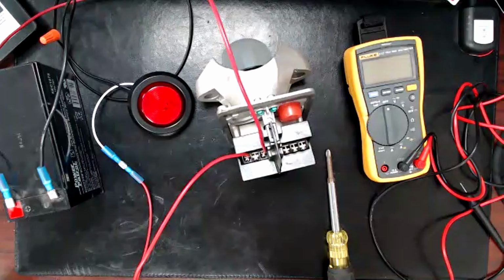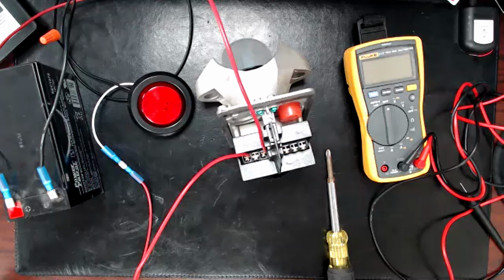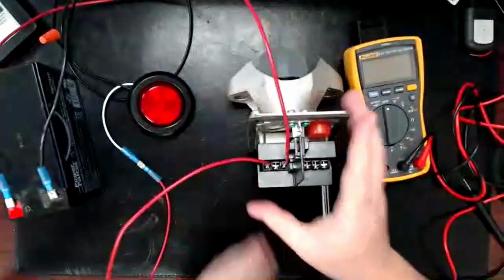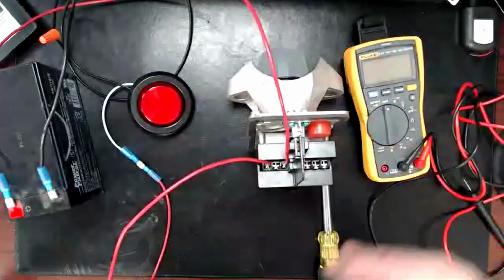That's what I'm saying. If you had 2 water flow switches, you can run it either way. Yes. So 2 water flow switches would follow the exact same principle as this if you had to wire it up this conventional way. And then you would just run a jumper over, and you would jumper from this common to the second water flow's common. And from this normally open, you would run a jumper to the second water flow's normally open. And then that way, if either water flow went into alarm, it would activate this light.